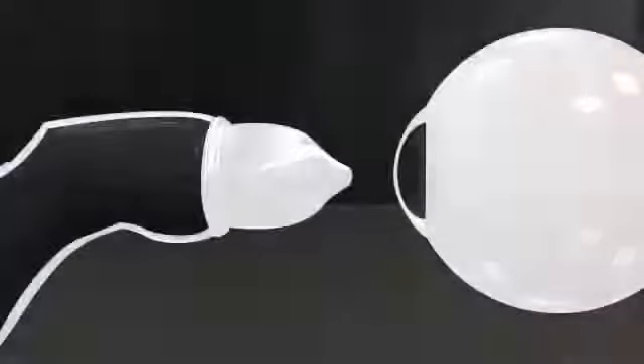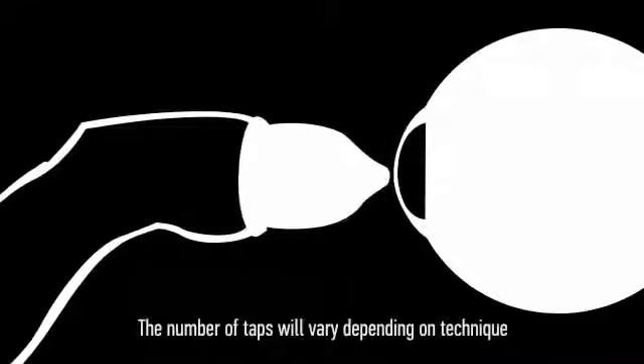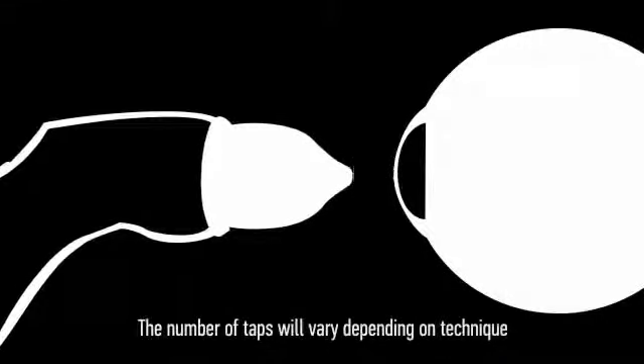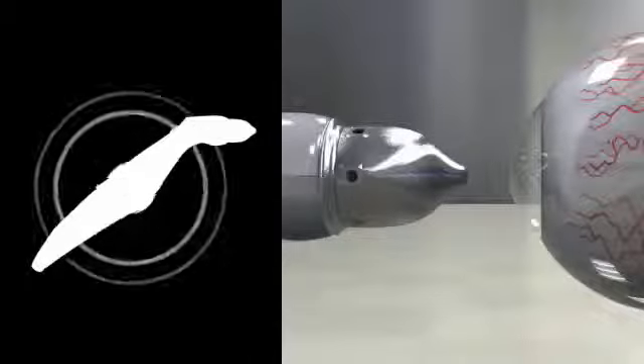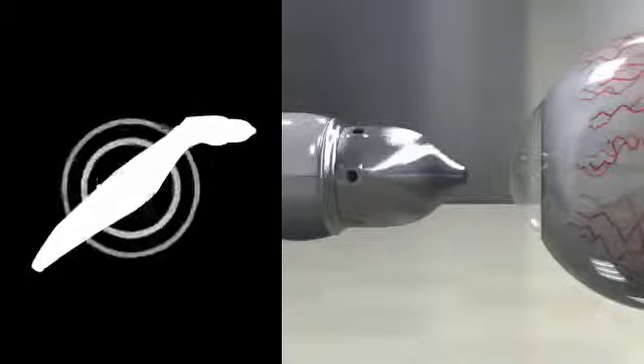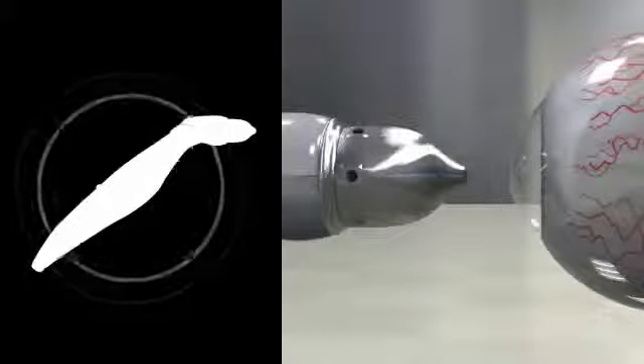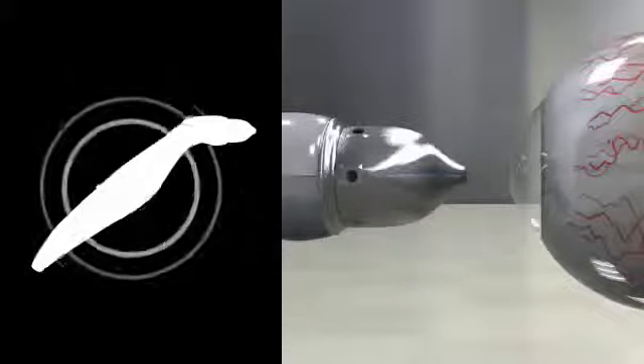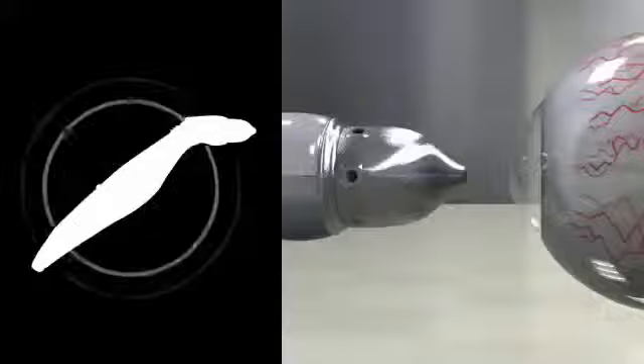After pressing the Action button, the AccuPen will beep twice, indicating that it is ready for measurements. Gently tap the transducer tip on the patient's cornea. The probe should be perpendicular and measurements should be taken at the center of the cornea. As you gently tap the cornea, you will hear short chirps followed by one longer chirp. The longer chirp indicates you have obtained an IOP measurement. The number of short chirps can vary.